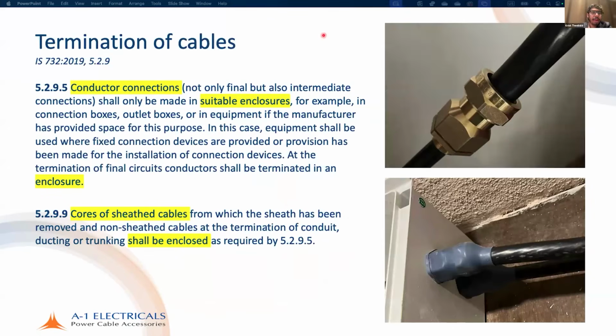So, terminations of cables. IS 732:2019, clause 5.2.9, says that conductor connections, so not only final conductors but intermediary connections as well, shall, and we know that shall is a requirement, be made in suitable enclosures, for example, connection boxes, outlet boxes, or in equipment if the manufacturer has provided space for this purpose. In this case, equipment shall be used where fixed connection devices are provided or provision has been made for the installation of these connection devices.